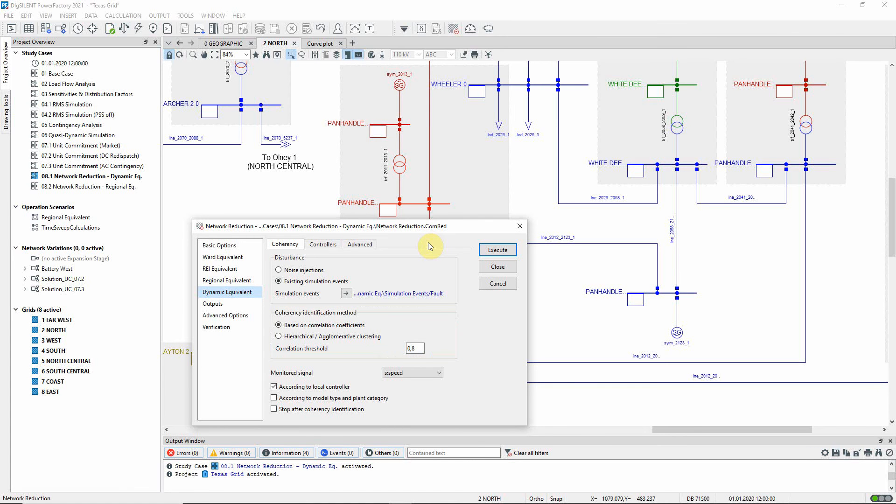The option selected here ensures that only machines with the same control mode, such as constant V or constant Q, will be aggregated. So unless all the generators in any particular group have the same control mode, the group will be represented by more than one replacement generator.